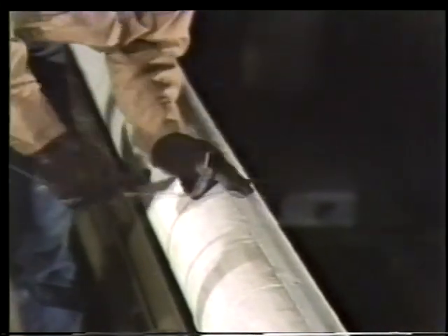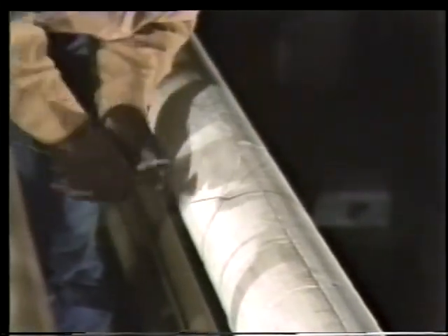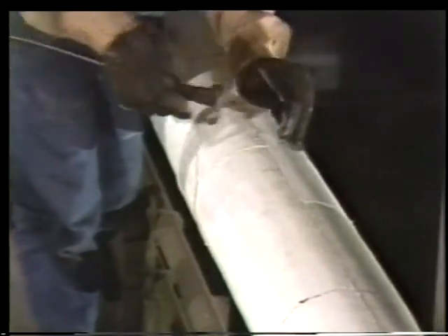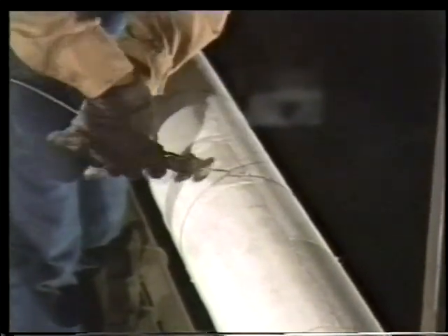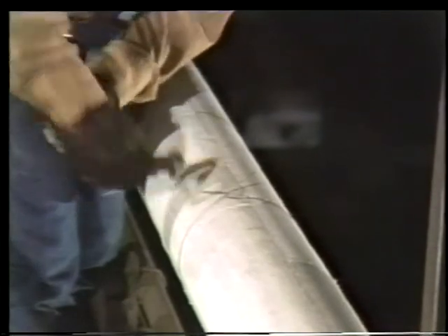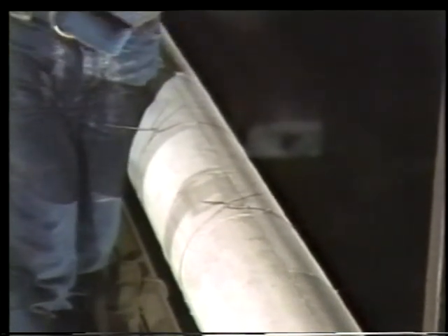The next section is mounted on the opposite side. The end joints are butted together tightly so the insulation will prevent heat losses as effectively as possible. The first wire holds the section together while the worker adds a second wire. Wires are spaced at intervals of 1 foot, about 1/3 of a meter. With sections of this size, that means 3 wires per section.